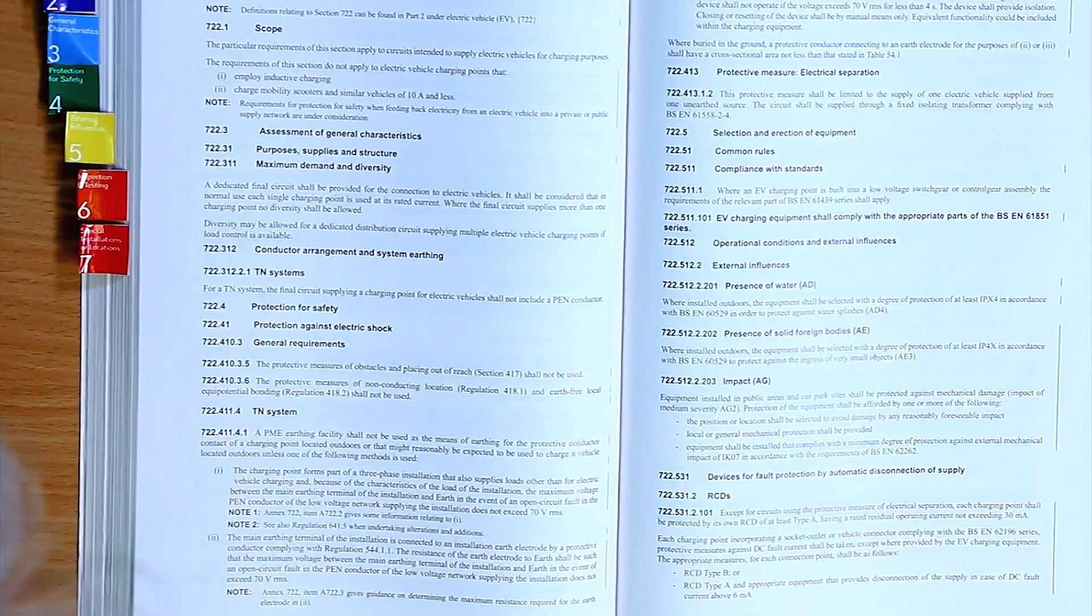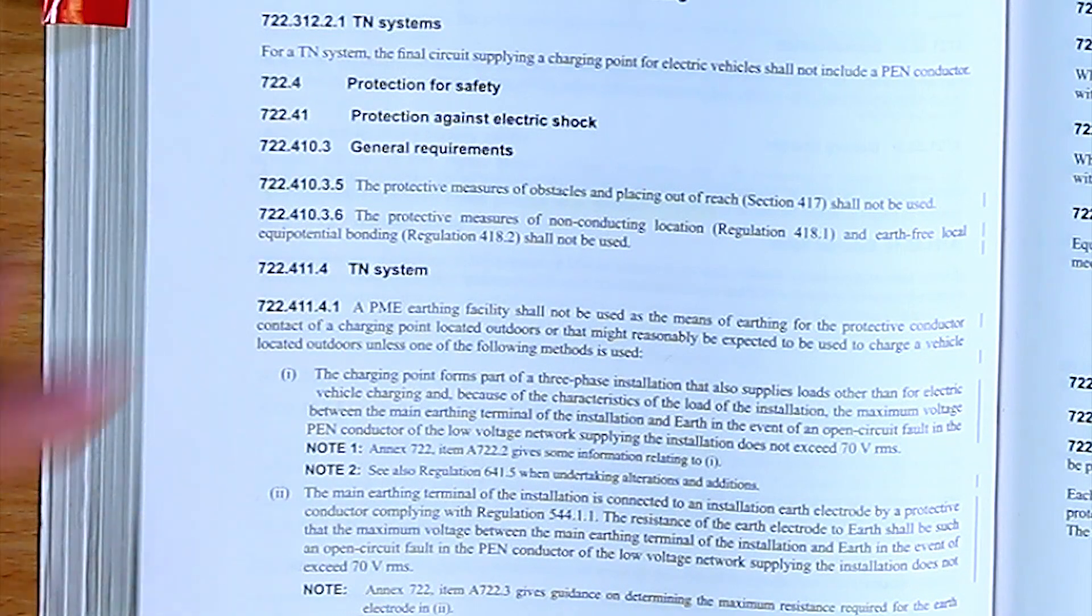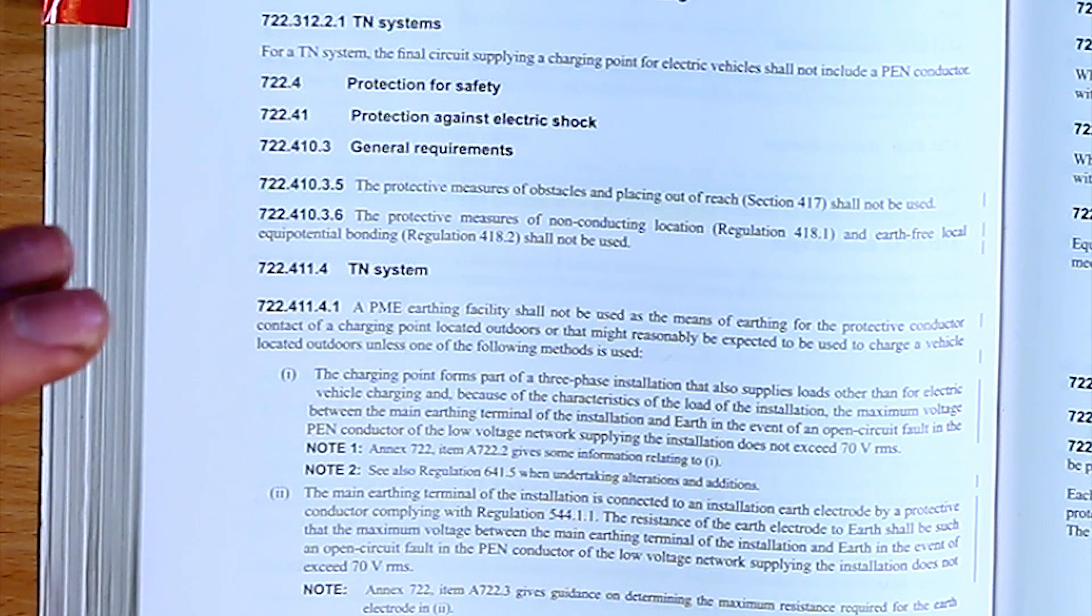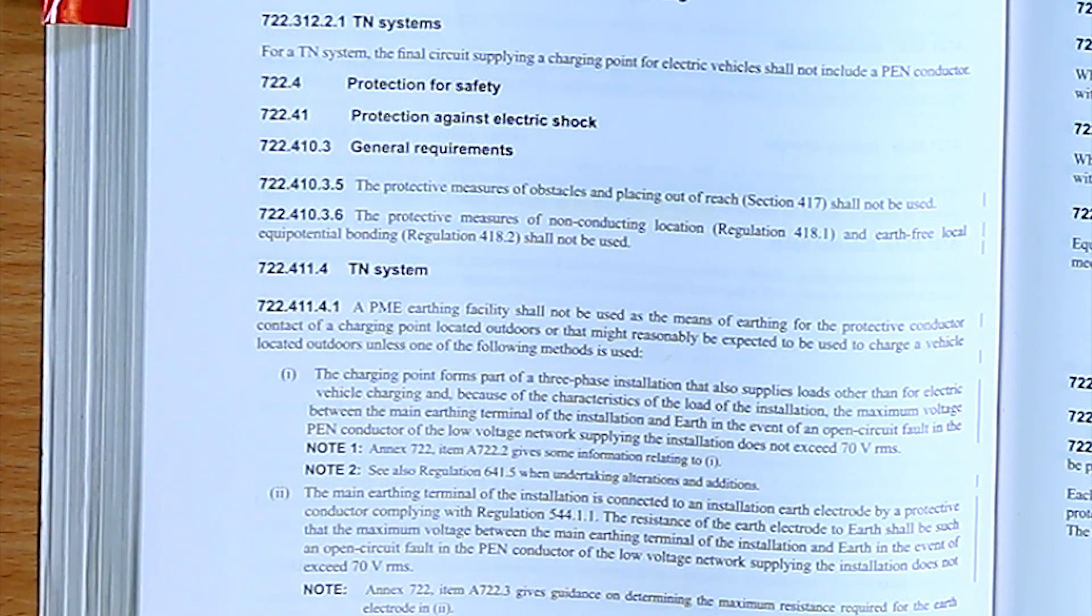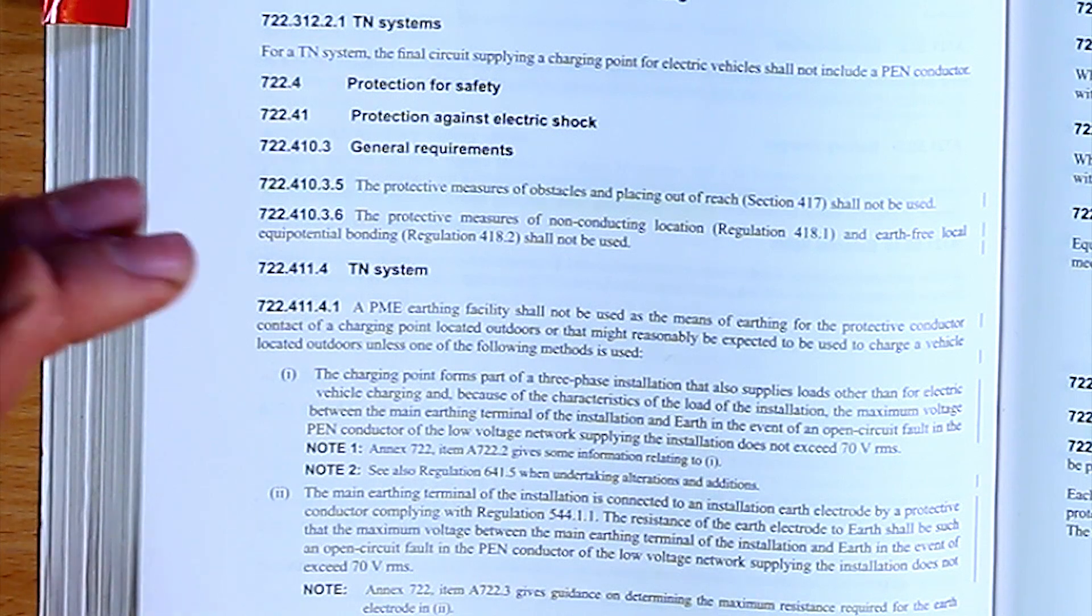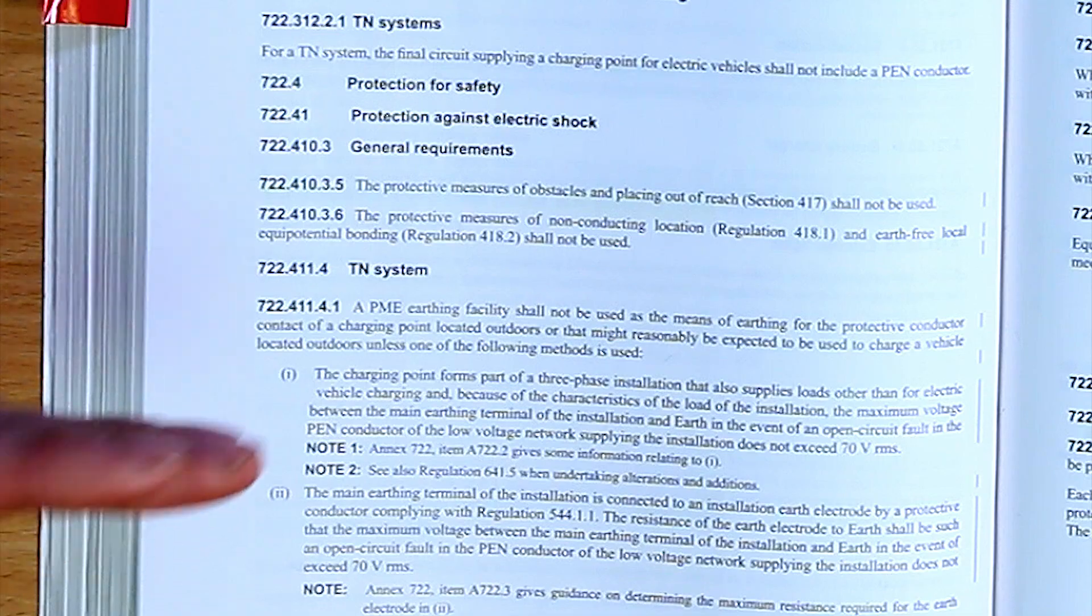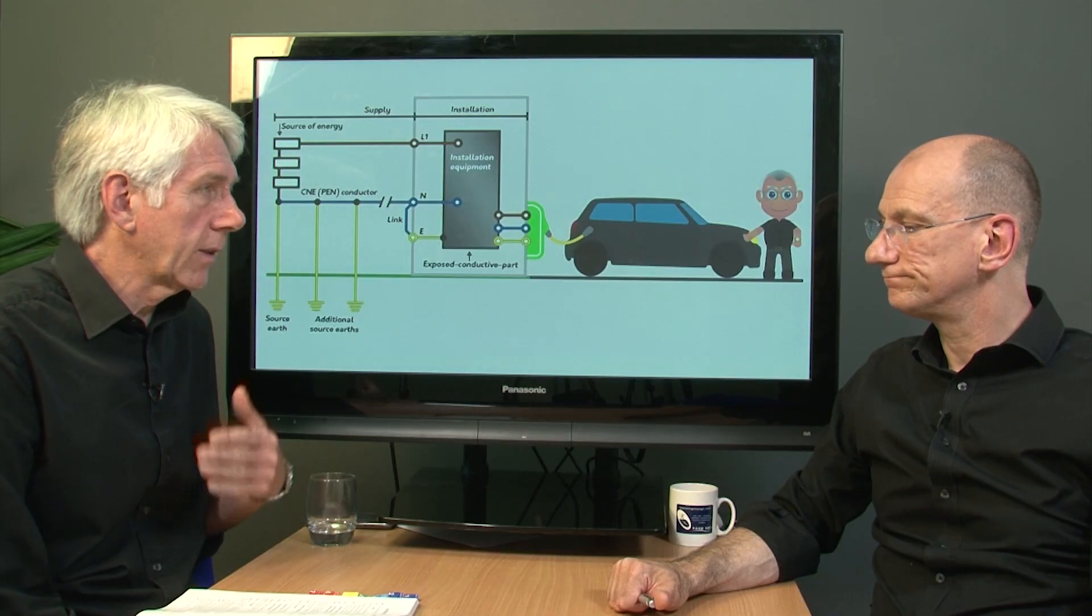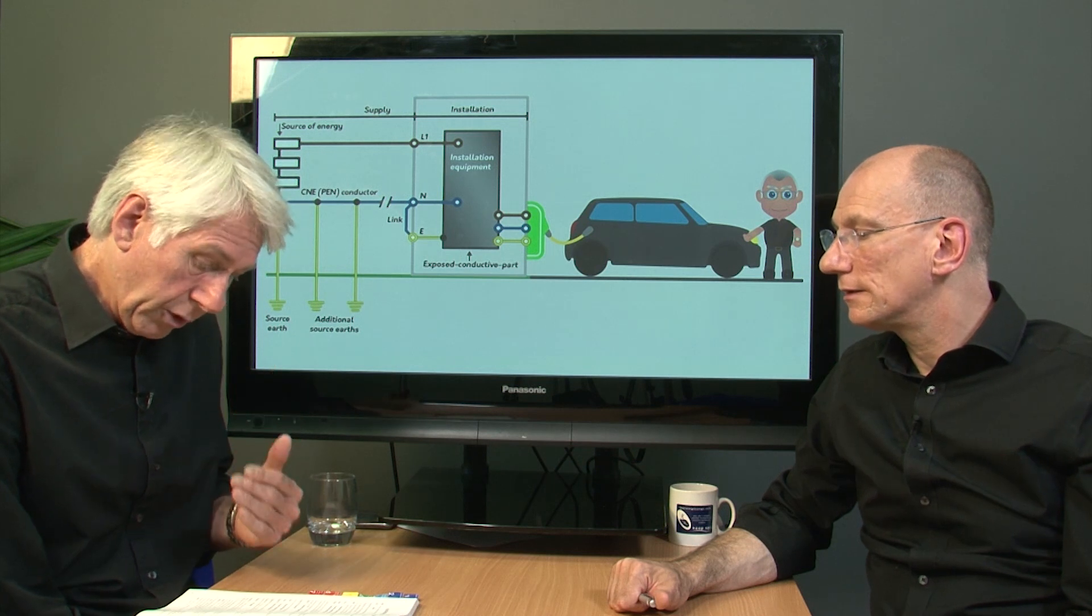And when we look to 722.411.4.1, it talks about that very situation in a TN system. A PME earthing facility shall not be used as a means of earthing for the protective conductor contact to the charging point located outdoors, although it might be reasonably expected to be used. And it gives us three options as effectively supplementary protection there, if we want to do that.